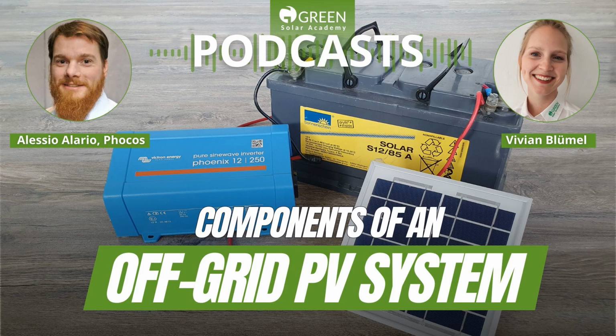First of all, we need an off-grid inverter which is bidirectional, so which is capable not only of sending power to your loads, but also of receiving power from the grid inverter. That's the first requirement. And second, we need to be able to control how much power is flowing. And that's where things get quite complicated, because we need to tell the grid inverter when to stop delivering power, because maybe the battery's full and the loads don't need all of that power. We need to do things like change the voltage or the frequency of the AC signal. So you need to really know what you're doing there. You need to know how to set up your off-grid inverter to be able to not only receive the energy from the grid inverter, but also to control it.